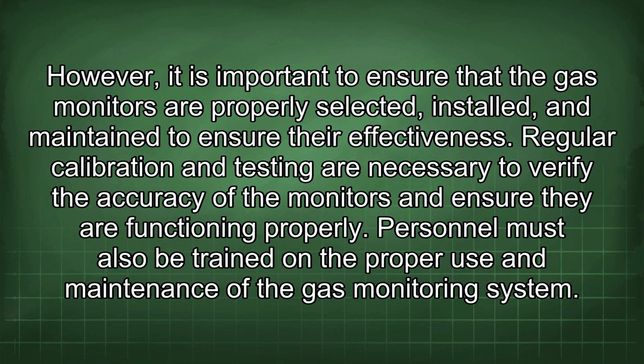However, it is important to ensure that the gas monitors are properly selected, installed, and maintained to ensure their effectiveness. Regular calibration and testing are necessary to verify the accuracy of the monitors and ensure they are functioning properly. Personnel must also be trained on the proper use and maintenance of the gas monitoring system.